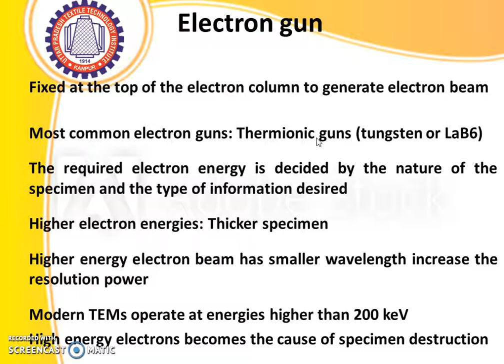Higher electron energy is required for thicker samples. A higher energy electron beam has a smaller wavelength, which increases the resolution power. Modern TEMs operate at energies higher than 200 kilovolts. High energy electrons can also become the cause of specimen destruction, so the optimum energy level is always preferred.